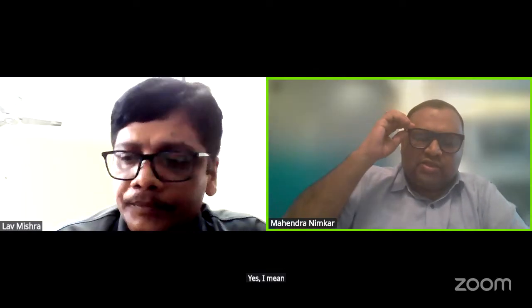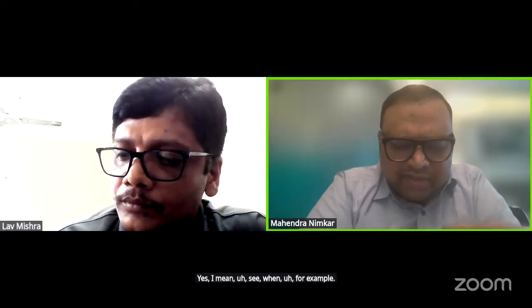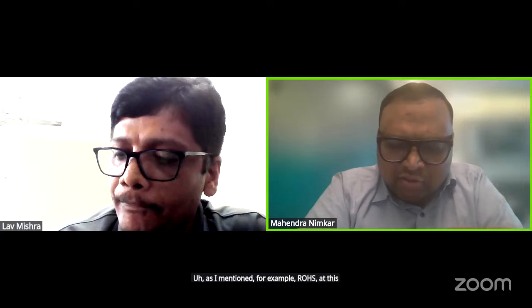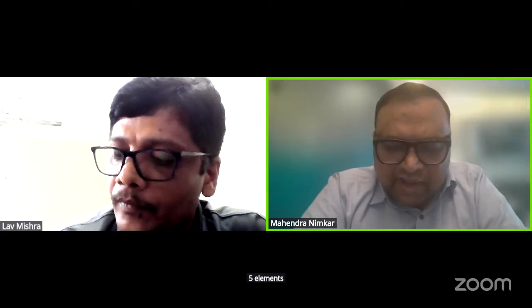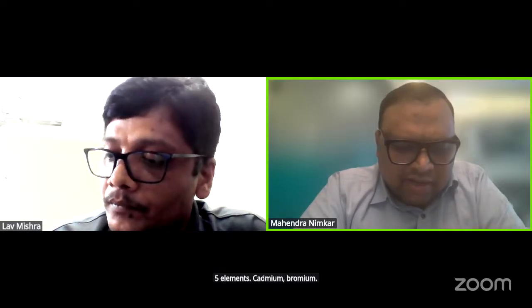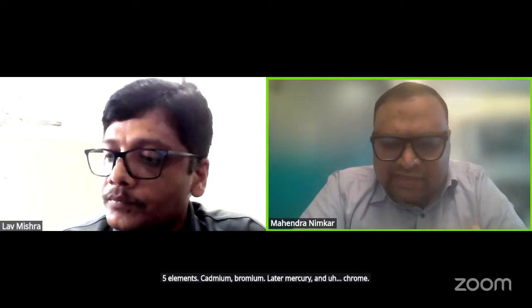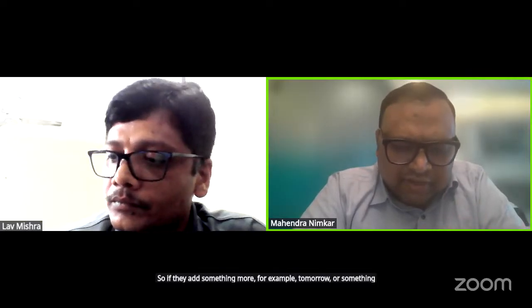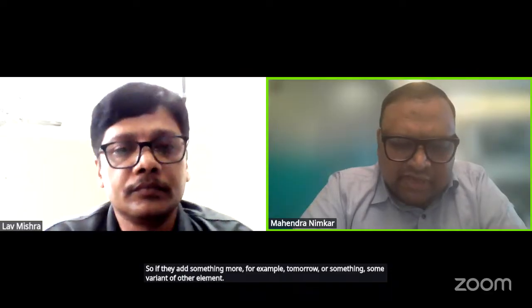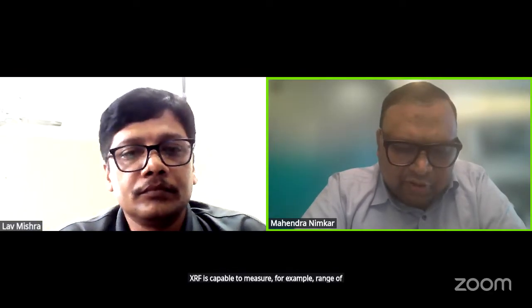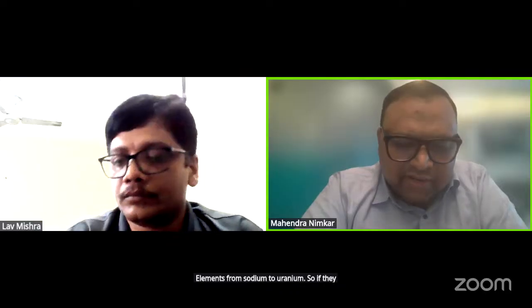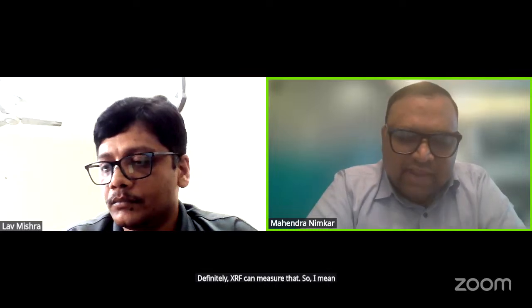Yes, for example, RoHS at this point of time is only talking about five elements: cadmium, bromine, lead, mercury, and chrome. If they add something more tomorrow, some other element, XRF is capable of measuring it. A benchtop XRF can measure elements from sodium to uranium. So if they add something in between, definitely XRF can measure that. If it fits in this range, XRF can do that.